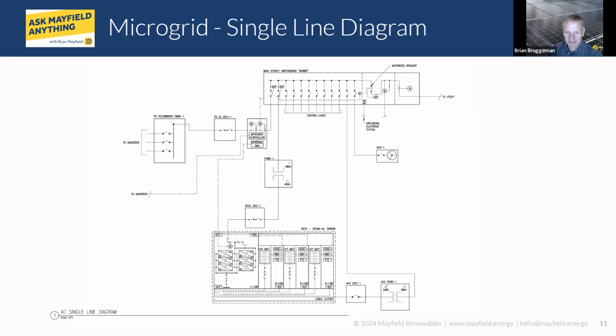The short answer is that some of the energy storage systems can produce a voltage that can damage electronics, so that needs to be filtered out before it gets to the electric grid. That's why these isolation transformers are there. There are several other reasons they could be included. When you're doing resiliency projects, some energy storage systems don't include a neutral, so we need to add a transformer to have the neutral to feed single phase loads, or to change the voltage. But in this case, it's 480 to 480, and this transformer was included for the neutral to feed single phase loads. Yep, that makes sense.